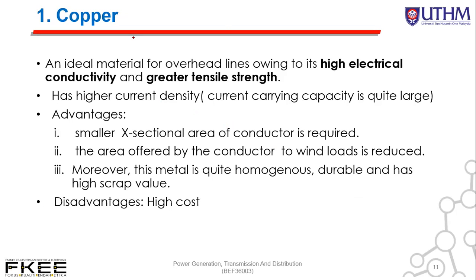So first, copper, an ideal material for overhead line owing to its high electrical conductivity and greater tensile strength. It has higher current density, which means the current carrying capacity is quite large. The other advantage is that a smaller cross sectional area of conductor is required, so only a small conductor is required. The area offered by the conductor to wind load is reduced. Moreover, this metal is quite homogeneous, durable, and has high scrap value. But the disadvantage is nothing but high cost.